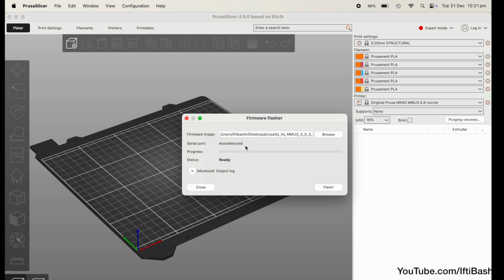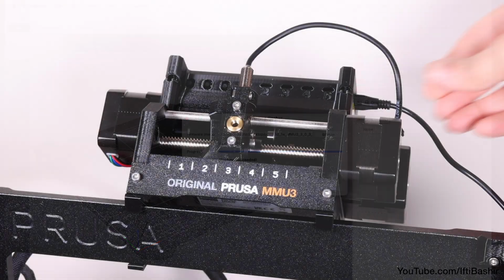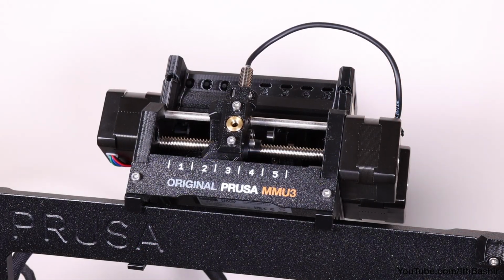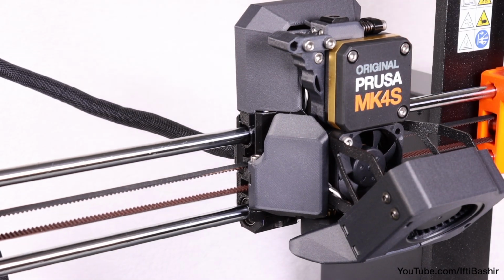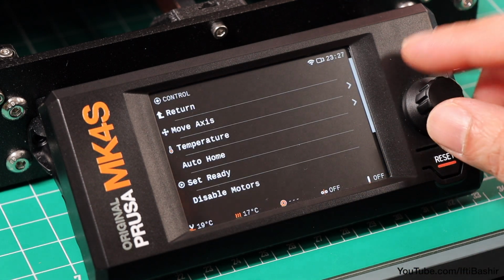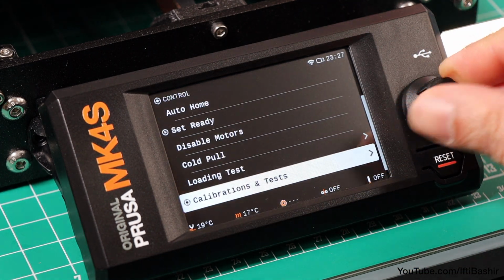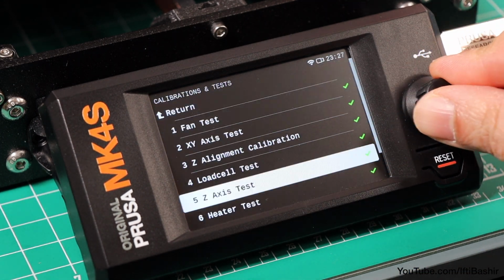as long as the USB cable is successfully connected, after which we can simply hit the flash button to begin the firmware application process. This doesn't take very long, and we're looking for the flashing succeeded message, as seen here. With that done, we can safely remove the USB cable from the MMU. Okay, so next we need to recalibrate the gearbox, considering we've been replacing parts inside. So navigate to Control, Calibration and Tests, and scroll down and select the gear's calibration.